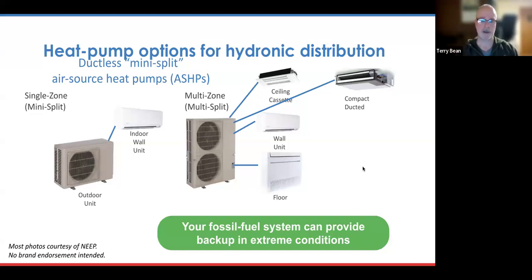And in this case, this pop-up that just came up in the slide here, what this is referring to is, when we're talking about the ability of a heat pump system in cold temperatures, what we're really talking about is its capacity. And that translates to how much heat it is delivering. Some systems are designed where they can deliver a similar amount of heating at very cold temperatures outdoors, when there is not so much heat energy available in that air. And then there are other heat pumps that cannot do that, or they're not designed to do that, maybe a better way to say it. So they won't stop working in colder temperatures, but the amount of heating that they supply would be reduced. So they might not be suitable for full-time heating.